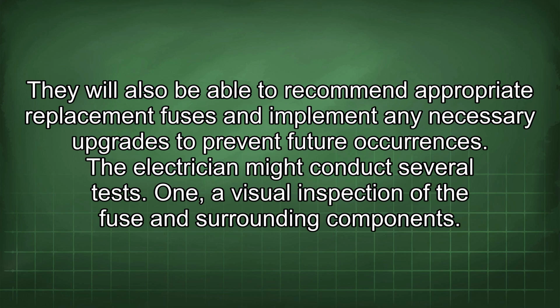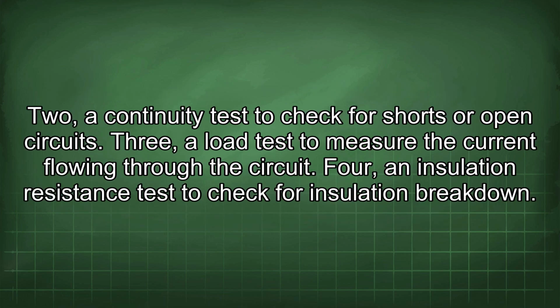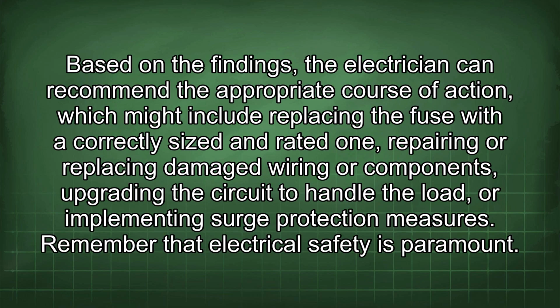1. A visual inspection of the fuse and surrounding component. 2. A continuity test to check for shorts or open circuits. 3. A load test to measure the current flowing through the circuit. 4. An insulation resistance test to check for insulation breakdown. Based on the findings, the electrician can recommend the appropriate course of action, which might include replacing the fuse with a correctly sized and rated one, repairing or replacing damaged wiring or components, upgrading the circuit to handle the load, or implementing surge protection measures.